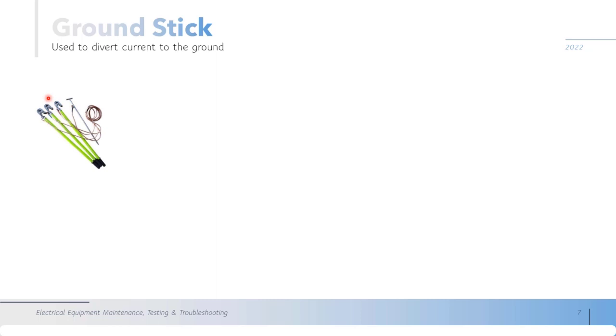So the first one is this type of ground stick, and this is used for medium voltage. You can see that you will be touching this part in black. This is an insulation part, even the body. And why do we need this distance between this part and this part? Because in high voltage the residual voltage in the line can reach bigger values, so you cannot approach the line like we approach at 220 volts, because there is an electric field. And if you get in contact with this electric field and you don't respect the minimum distance, the air that is insulating this electric field will be disrupted and there will be charge passing through your body from the line to the ground. So you will also get electrocuted even if you're not touching the line.